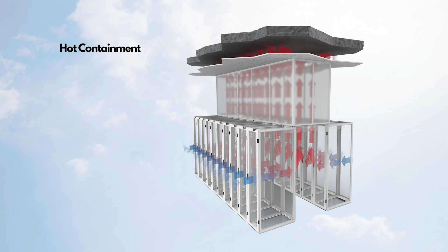So normally what we see now is that you have a fan wall in the white space area that pushes cold air into the white space. This cold air will go through the cabinets, and the hot air will be contained and go through a vertical containment. Then you can reuse this hot air throughout the entire facility, because it goes through a false ceiling.